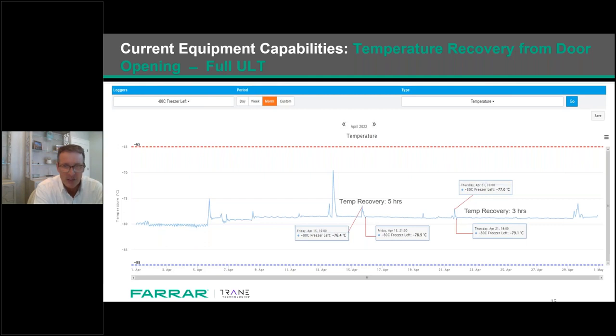And then, as you can see, it took anywhere from 3 to 5 hours. We represent two door openings here from a data logging system, and it was a 5 hour and a 3 hour temperature recovery. But again, it depends on the duration of the exterior door being open, as well as how much product was added inside. There are several vertical spikes on this graph, and they're associated with door opening and possibly, again, warm product being added inside.